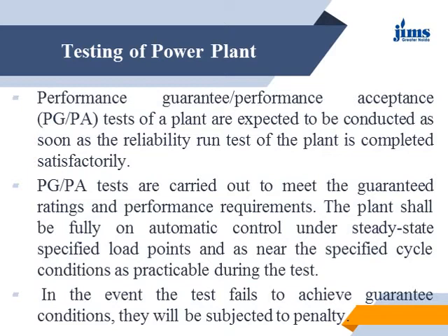In the event the test fails to achieve the guarantee condition, they will be subject to penalty. Means what? Those who are the quality inspectors, or those persons who come from outside to audit the power plant, first test the power plant, and there are two limits. One is from the power plant management side, that this will be the performance and we can guarantee this performance. And one is the acceptance level.